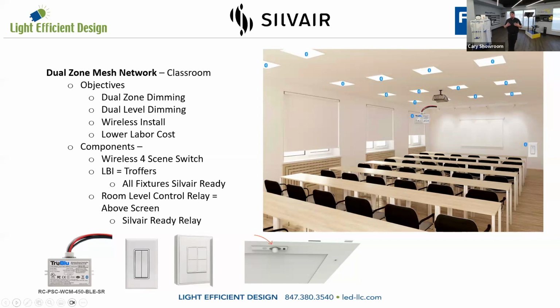For the downlights or the trim or the track lights by the presentation area, we actually use what's called room level control. That's a big box or relay that can control a lot of power, this one's about 20 amps, and it can handle about 150 milliamps of sink, so it can control a ton of fixtures.